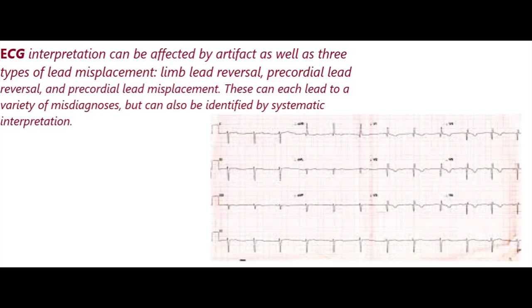Next are limb lead reversals. Swapping limb leads can drastically alter the ECG. Right arm and left arm reversal results in negative P and QRS waves in lead 1, and reversal of a limb with a neutral lead again disrupts Einthoven's triangle, causing distorted signals, potentially low voltage or pseudo-asystole, that is, a flat line in the lead.